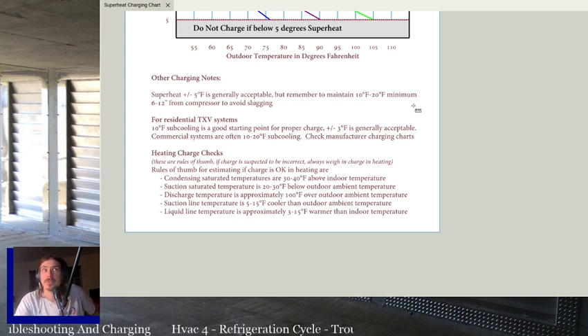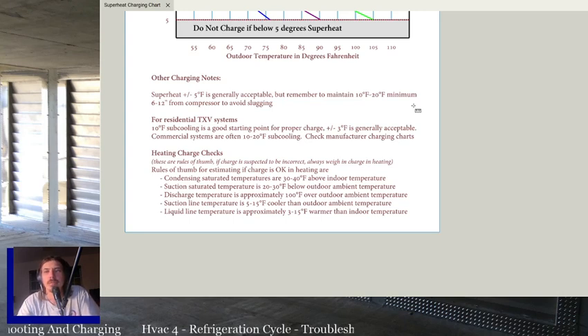I have seen systems with 10, 11 degrees of subcooling where if you got a sight glass, you'll still have some flash gas in the sight glass because it's a longer line set or something like that. So you may need to push subcooling a little bit so that you've got a solid column of liquid to the metering device. But in general, if you're between 7 and 13, it should work as intended. And if you've got issues with the system working as intended with a subcooling of 7 to 13 degrees, and it's not cooling properly, it's probably not the charge.